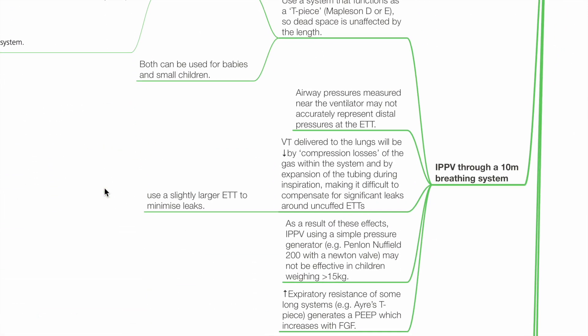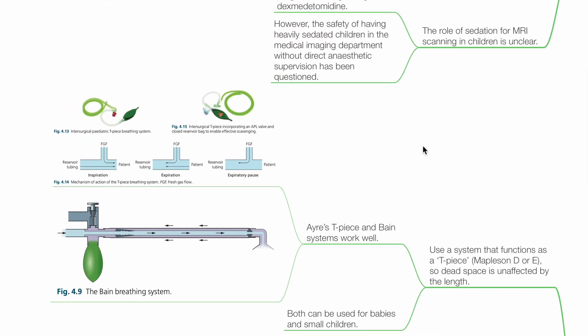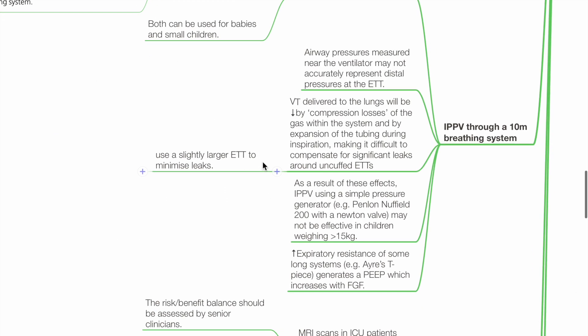IPPV through a 10-metre breathing system: use a system that functions as a T-piece so dead space is unaffected by the length — examples include the Ayre's T-piece and Bain system. Both can be used for babies and small children. Airway pressures measured near the ventilator may not accurately represent distal pressures at the ETT. Tidal volume delivered to the lungs will be reduced by compression losses and expansion of tubing during inspiration. This makes it difficult to compensate for significant leaks around uncuffed ETTs — use a slightly larger ETT to minimize air leaks.